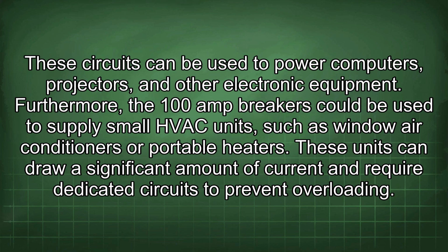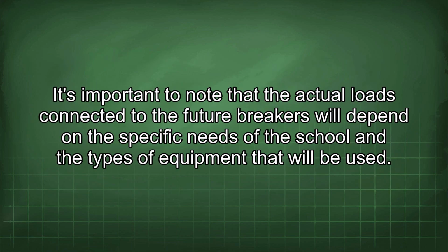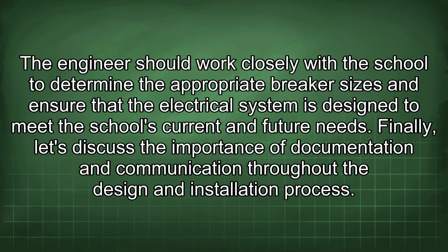Furthermore, the 100 amp breakers could be used to supply small HVAC units, such as window air conditioners or portable heaters. These units can draw a significant amount of current and require dedicated circuits to prevent overloading. It's important to note that the actual loads connected to the future breakers will depend on the specific needs of the school and the types of equipment that will be used. The engineer should work closely with the school to determine the appropriate breaker sizes and ensure that the electrical system is designed to meet the school's current and future needs.